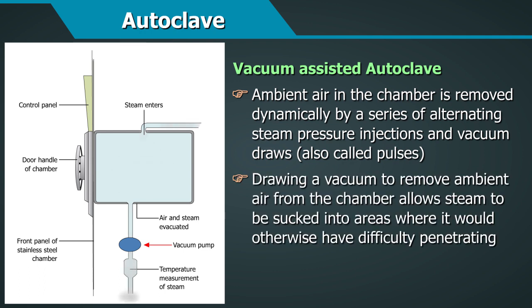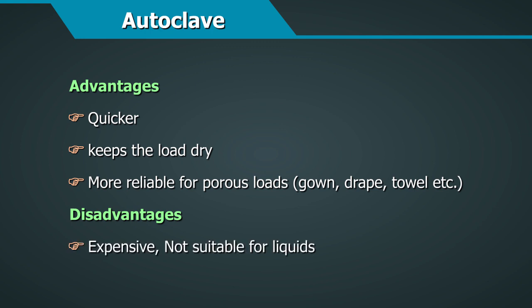The vacuum-assisted autoclave removes ambient air from the chamber dynamically by a series of alternating steam pressure injections and vacuum draws, also called pulses. Drawing a vacuum allows steam to be sucked into areas where it would otherwise have difficulty penetrating, and steam fills the vacuum almost instantaneously. Advantages include being quicker and keeping the load dry, and it is more reliable for porous loads such as gowns, drapes, and towels. The disadvantage is that it is more expensive and not suitable for liquids.